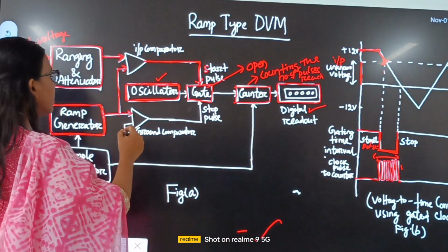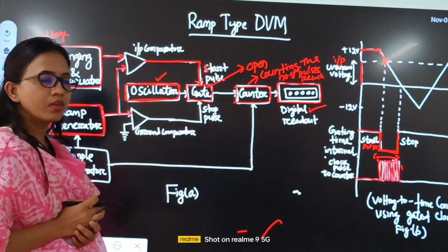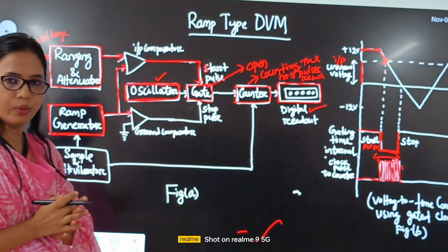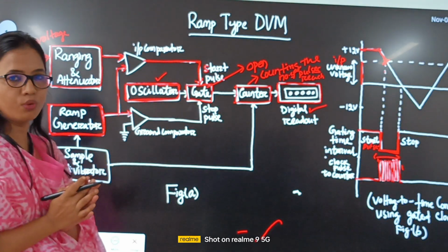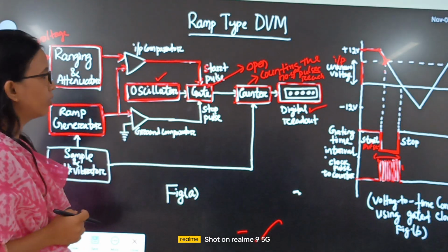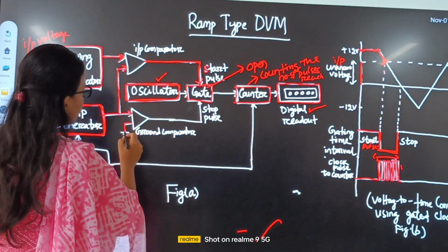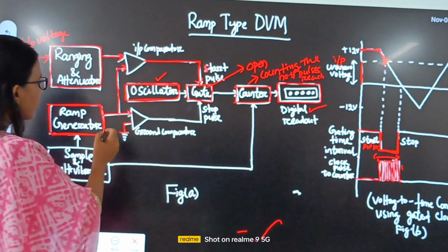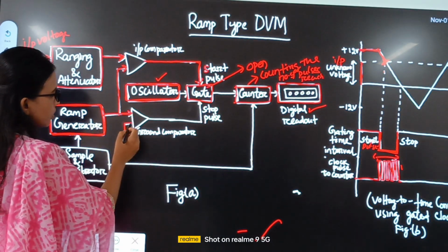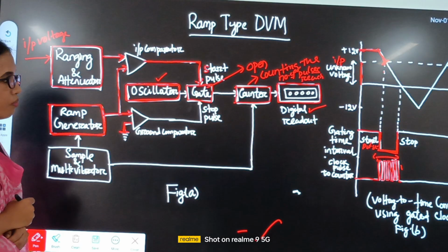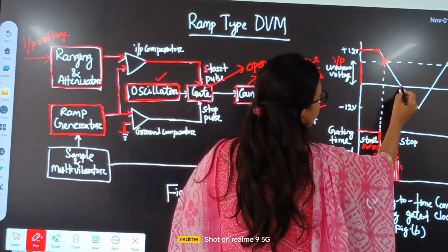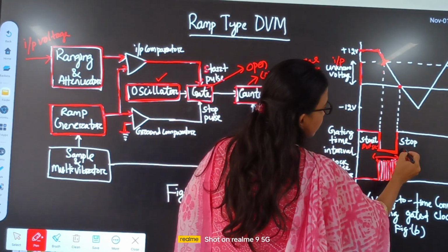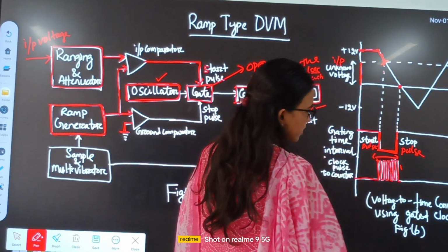Okay. So now when will it be stopped? It will be stopped by the ground comparator. As a measure of the ramp voltage, it always measures slowly as it goes towards the negative, so it will also be compared to ground. That ramp signal is also given to the ground comparator, which compares it to 0 volt. When the ramp reaches 0 volt, it gives a stop pulse.